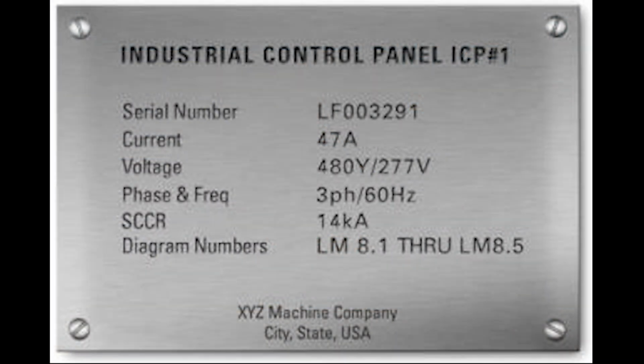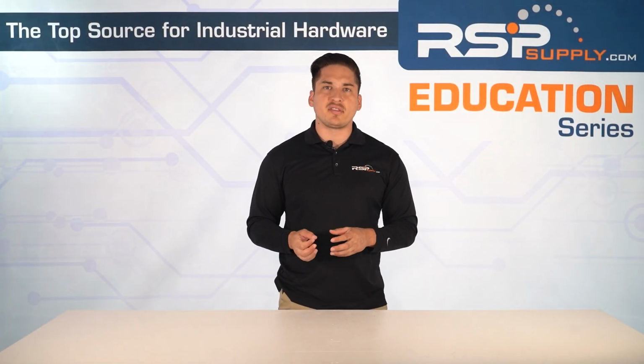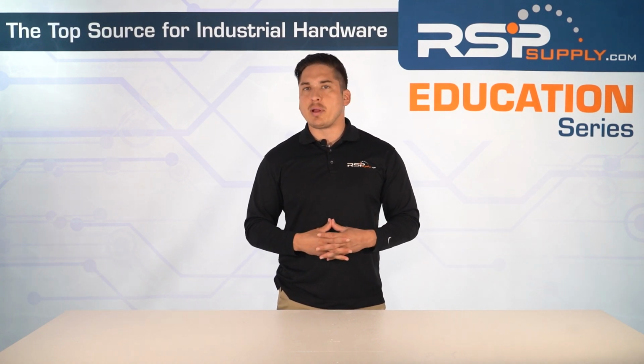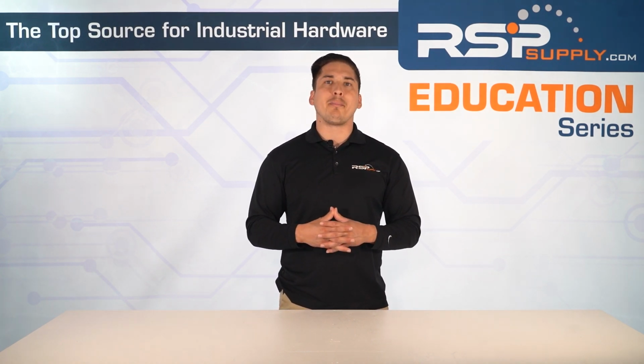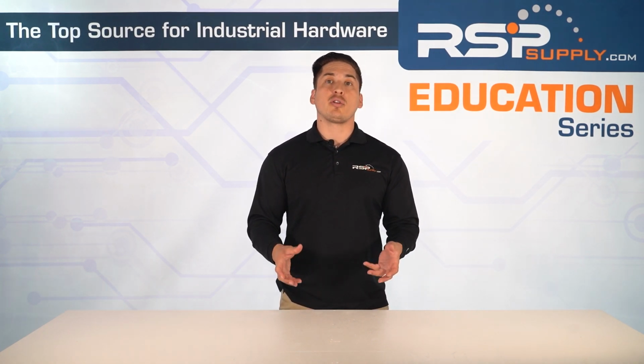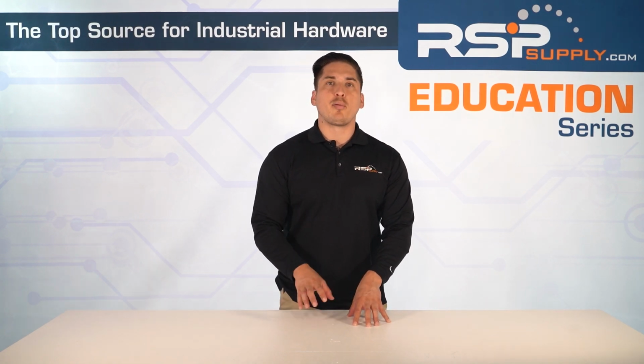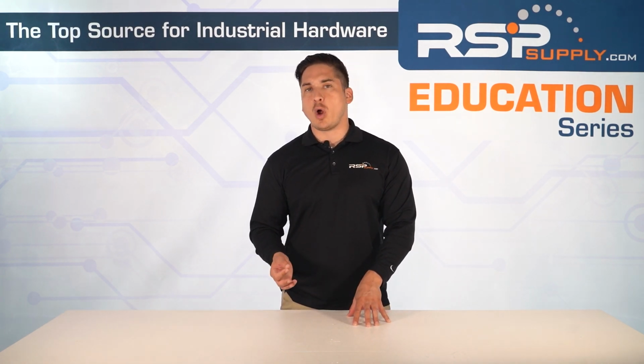Don't skip over short circuit current ratings or SCCR. If your disconnect switch isn't backed up by a breaker or fuse system that protects it, it needs to be able to stand up to the worst case fault current by itself. This is a short circuit current rating. Really important for keeping things safe when things go wrong.